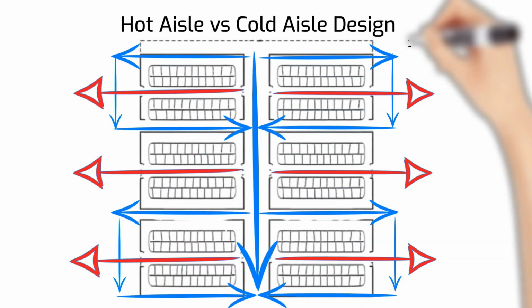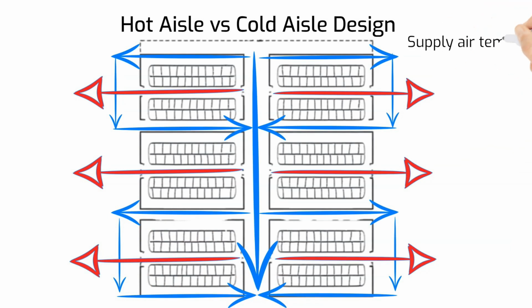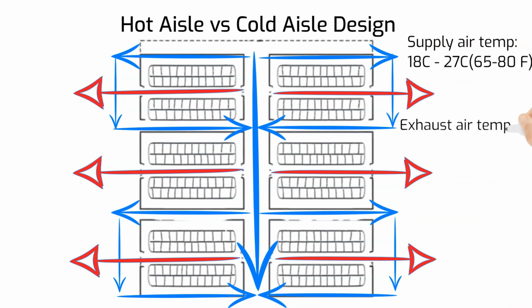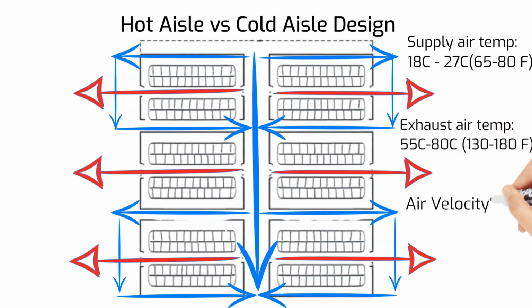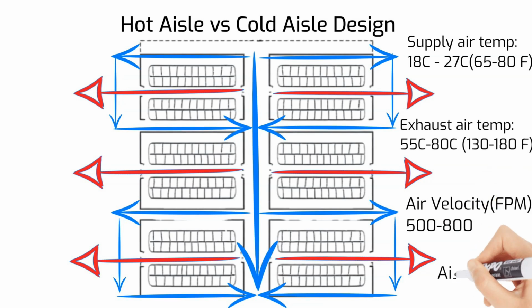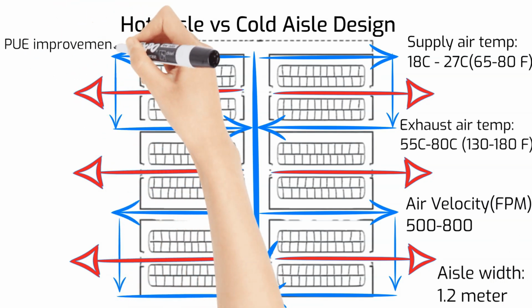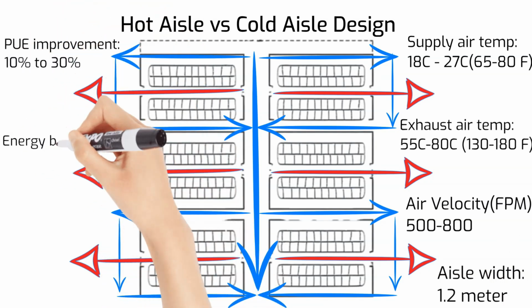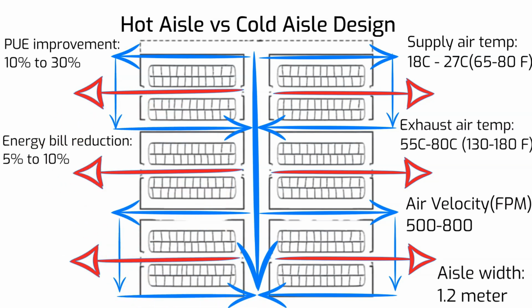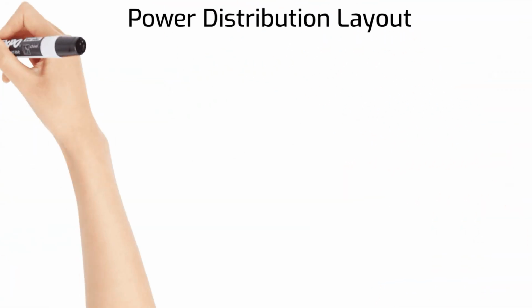The airflow volume required for exhaust must equal the sum of the airflow from all miners in the facility. The cold aisle should maintain an air temperature between 18 Celsius and 27 Celsius. Hot exhaust air from ASICs typically ranges from 55 Celsius to 80 Celsius. Recommended intake velocity at louvers is between 500 to 800 fpm. Exceeding 1000 fpm can increase static pressure and energy costs. Recommended aisle widths are at least 1.2 meters. Hot aisle containment can improve power usage effectiveness (PUE) by 10% to 30%, moving facilities closer to an ideal PUE of 1.0.